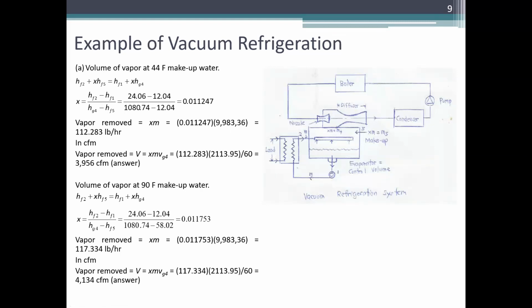112.283. So, and cubic feet per minute, this is V is equal to X, M times VG4. So, yan. So, 112.283 times 2113.95 over 60 kasi CFM tayo. Utang yung ano. Standard units yan. 3,956 is CFM. Now, the volume of vapor at 90 Fahrenheit makeup waters.